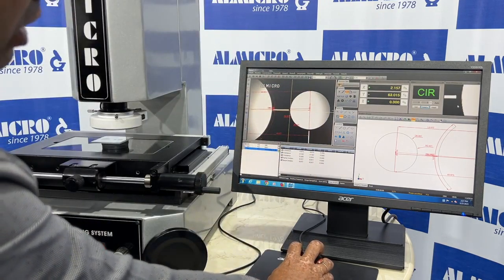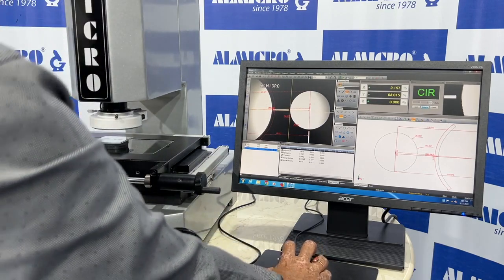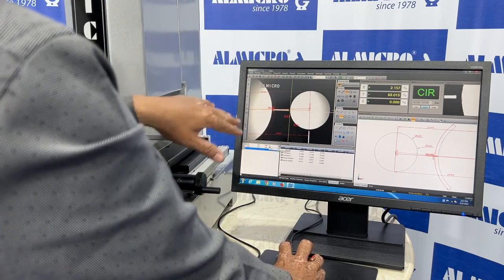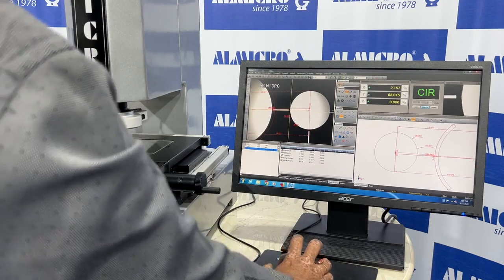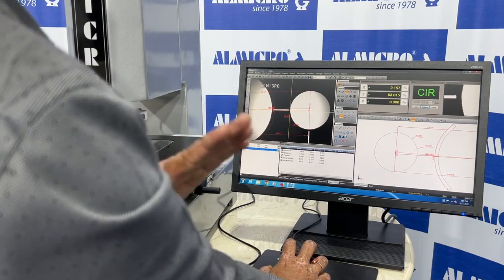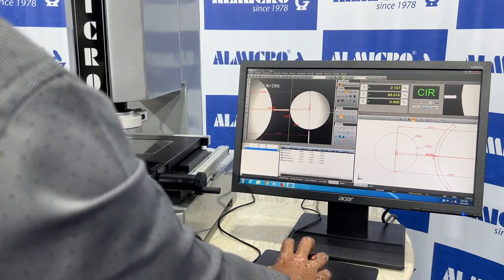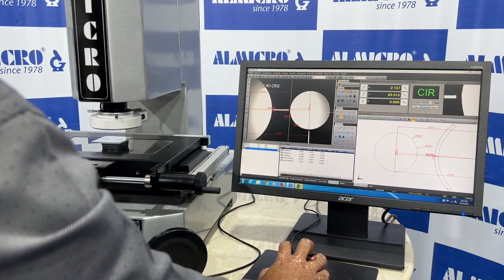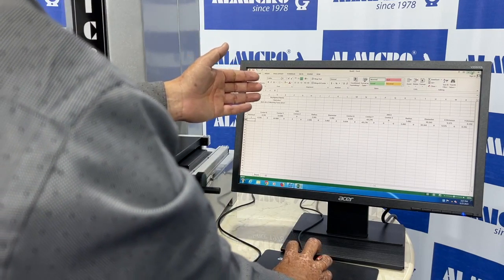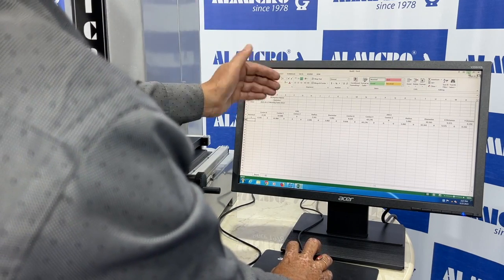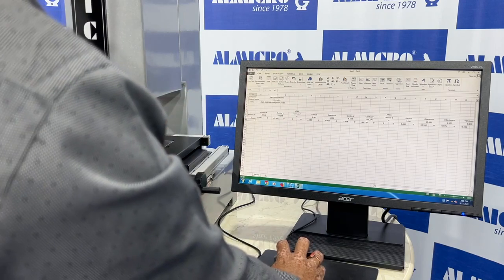This window is for the profile projector type — manual measurements. This window is the graphical measurements window. This window is the single result measurements. This is the long results or all-results window. These are the processes to take all different measurements. Finally, if you need the result, go to CAD export to Excel, just click here, and your Excel report will generate. You can also take your graphical represented window and a photo of the represented window will be captured by the instrument.